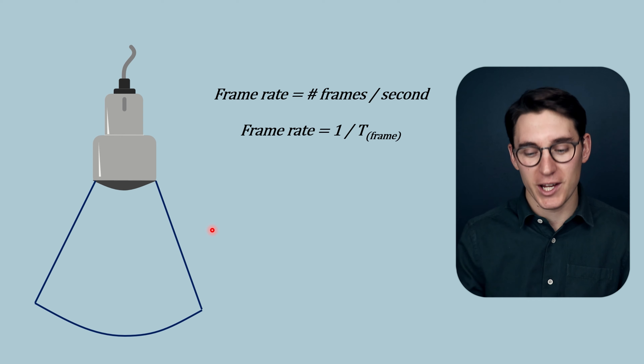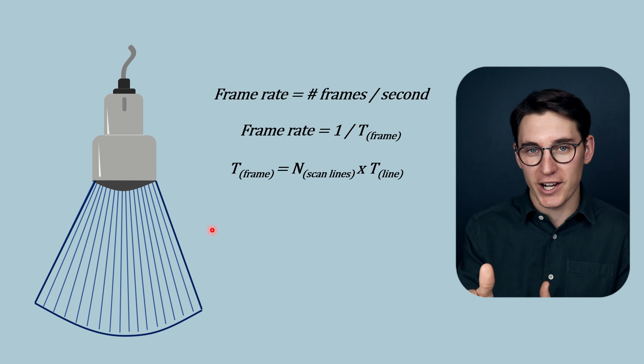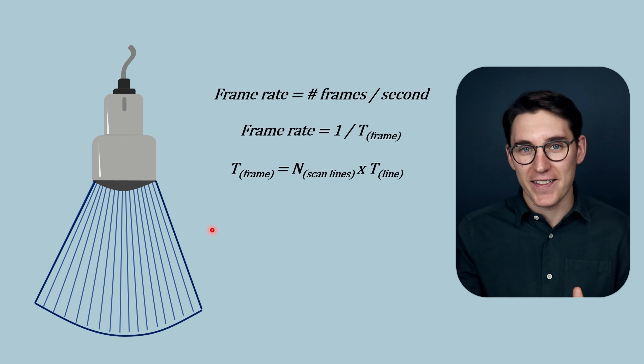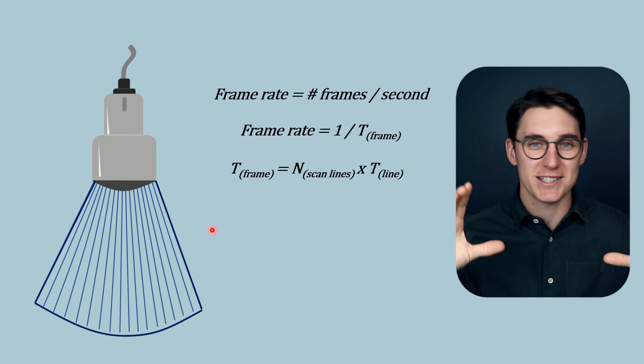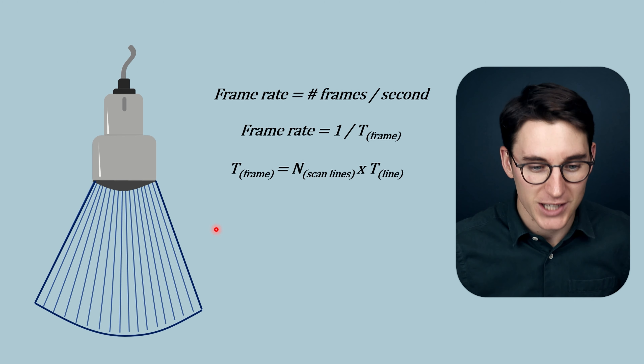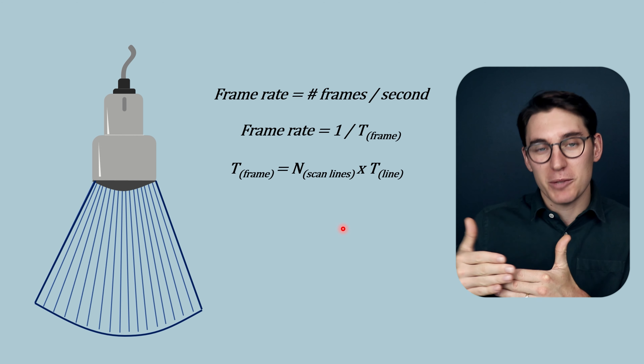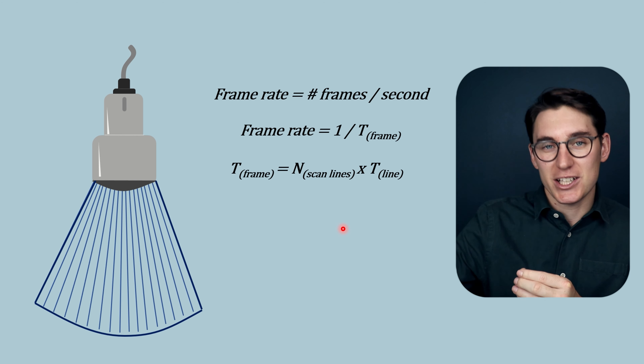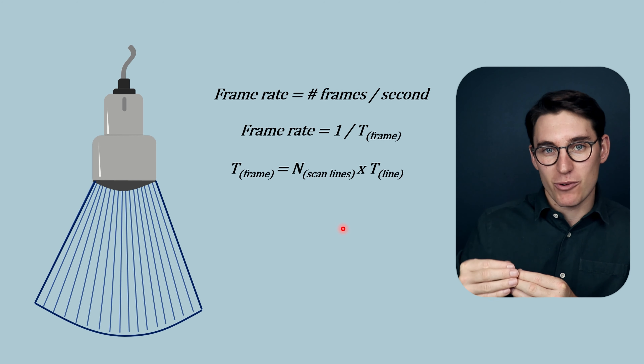So what goes into acquiring a single frame? Acquiring a single frame takes multiple A-lines of data stitched together to create that single frame. The time it takes to create a single frame is the number of scan lines within our field of view multiplied by the time it takes to acquire a single scan line. To acquire a single scan line, the ultrasound machine emits a pulse into the tissue, which travels to a set depth and reflects off a surface, returning back to the machine. That round trip time is the time it takes to acquire a single line of ultrasound data.